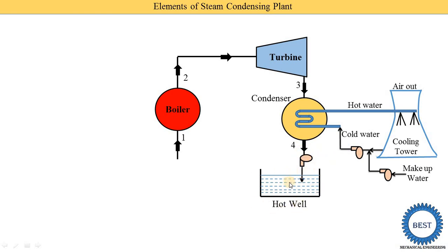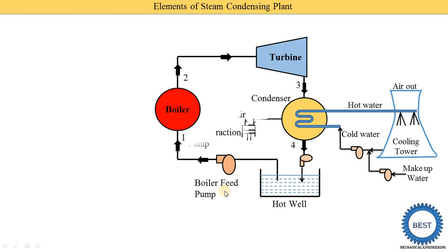In the hot well, the water is collected, and this water is again supplied to the boilers by using the boiler feed pumps. The next component is the air extraction pump. We need to maintain the condenser pressure below atmospheric pressure — this is called vacuum pressure. So we need to remove the air from the condenser, and for that purpose we use the air extraction pump.